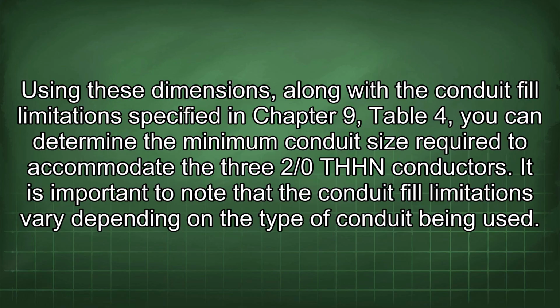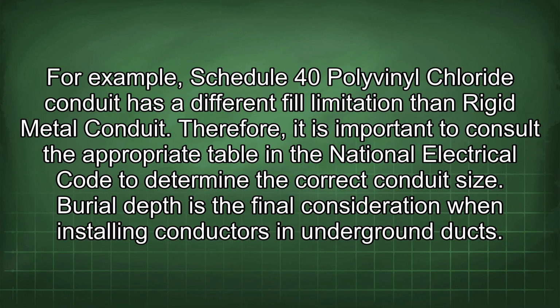It is important to note that the conduit fill limitations vary depending on the type of conduit being used. For example, Schedule 40 polyvinyl chloride conduit has a different fill limitation than rigid metal conduit. Therefore, it is important to consult the appropriate table in the National Electrical Code to determine the correct conduit size.